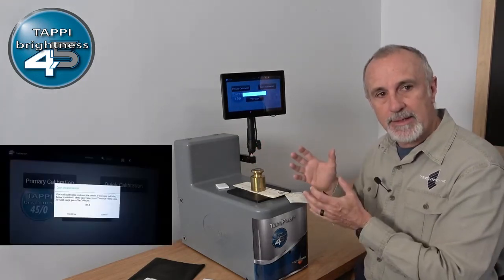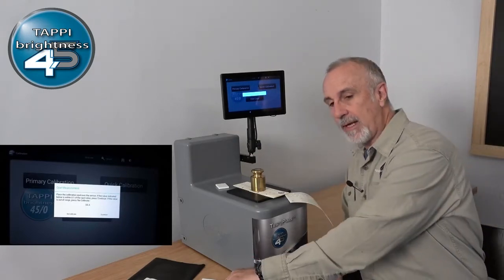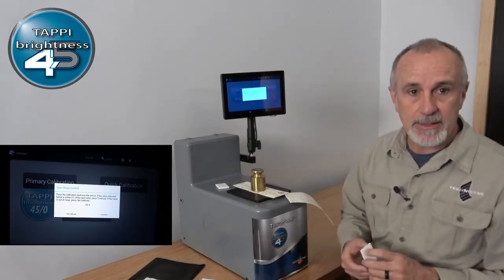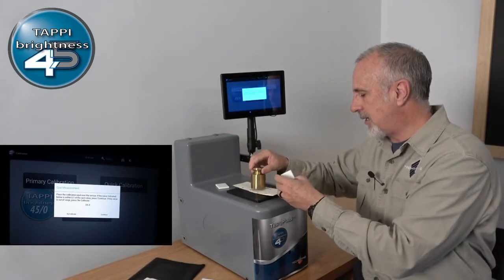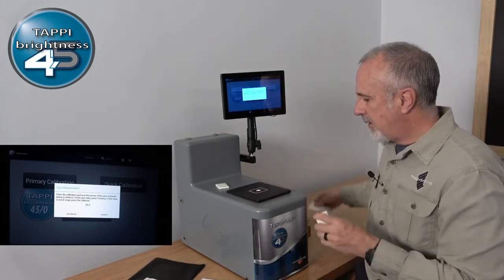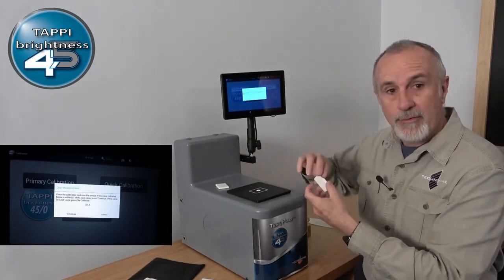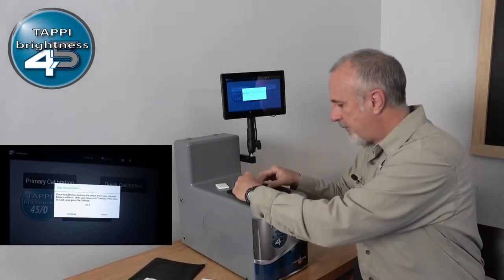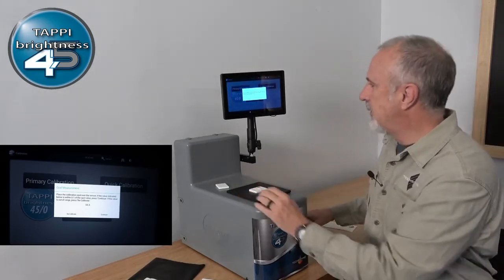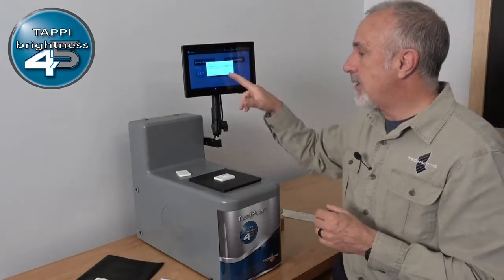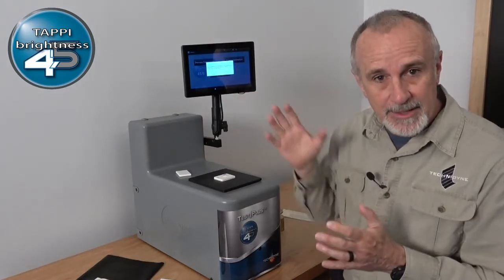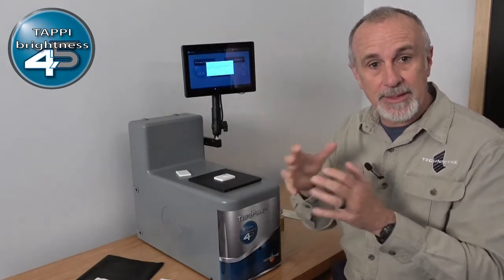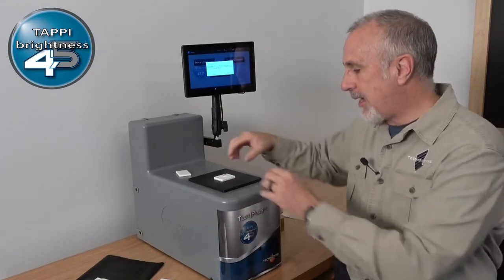Once that's completed, it will tell me to load the Opal standard that came with the set of calibration standards. All right, so I will take that off now. I will load the Opal. The value for this is 84.4. I will put that on the instrument. And now that reads 84.5, so I'm within a tenth, and that's what it states in the instructions. So if you're within a tenth, you're ready to move to the next step.